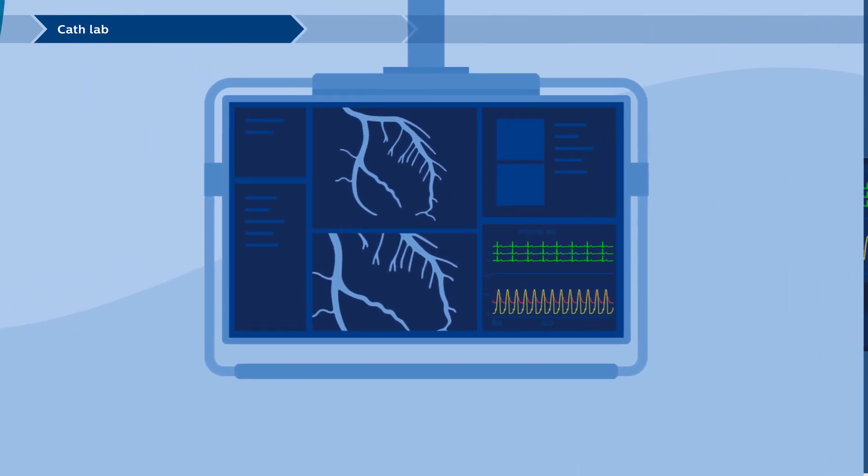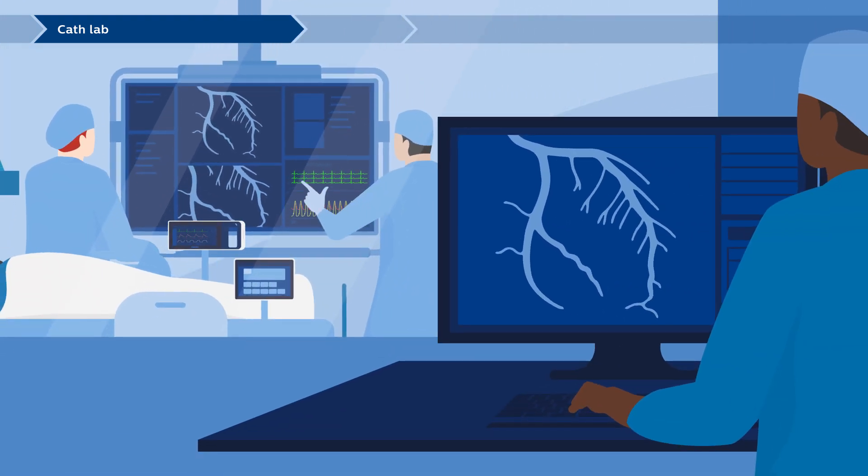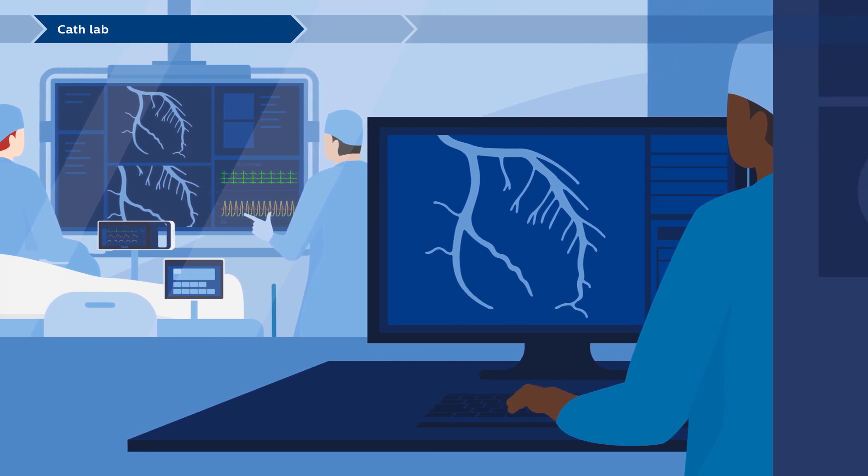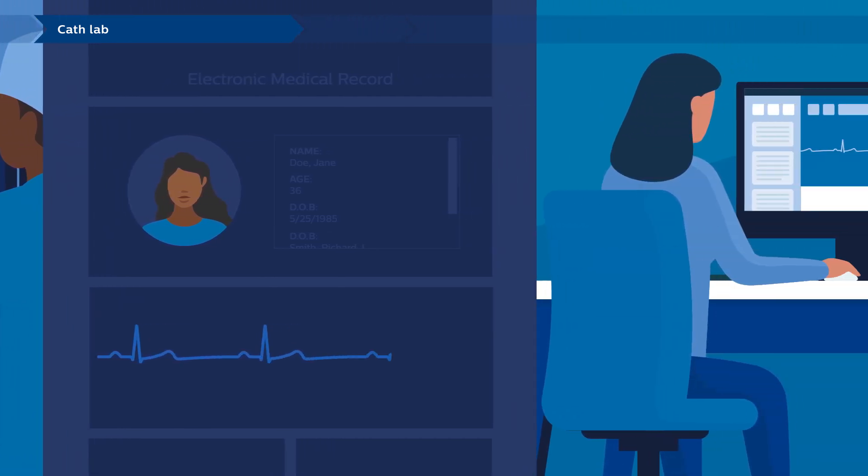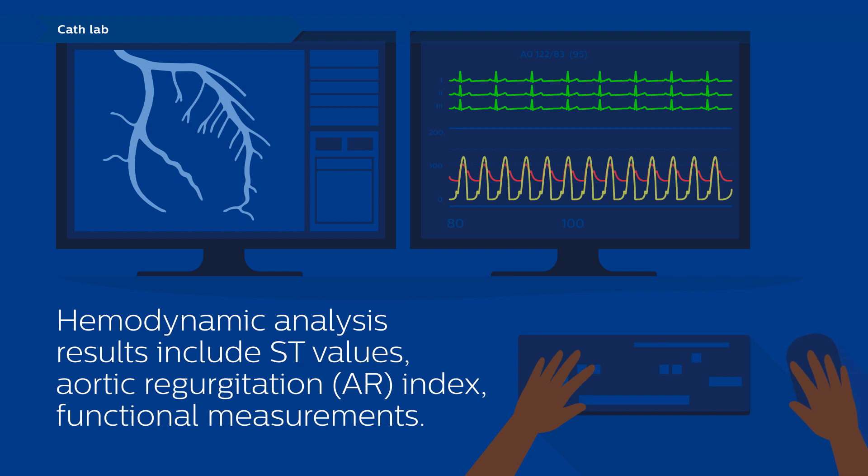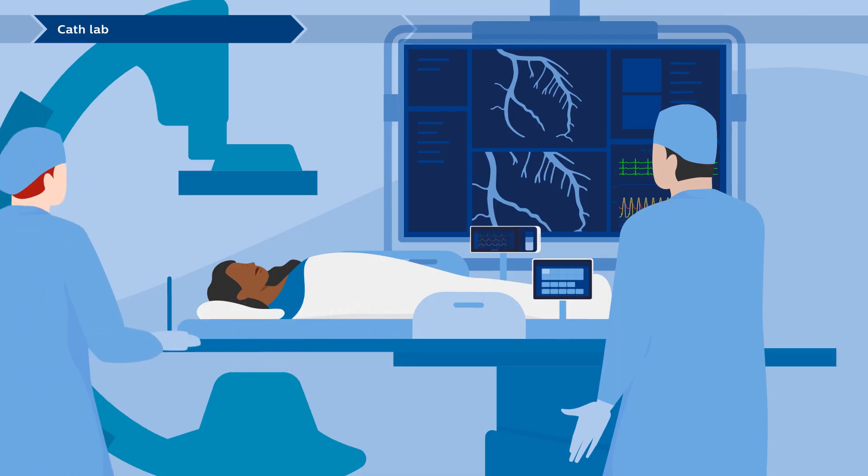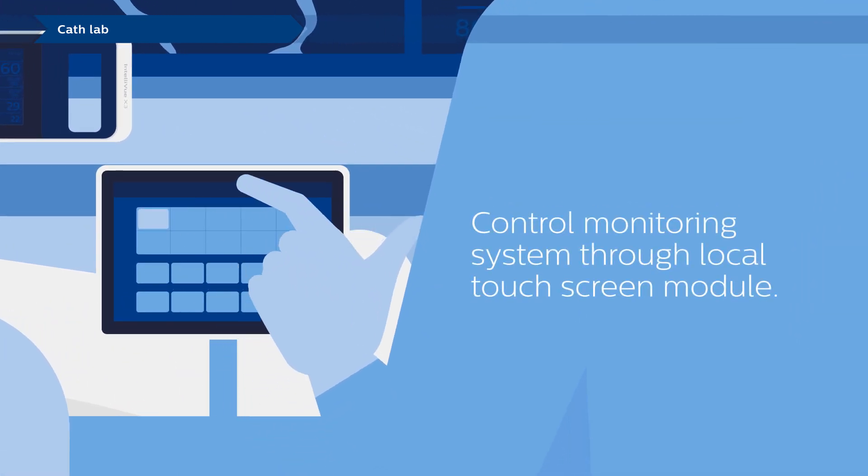Throughout the procedure, cath lab staff can monitor the patient's hemodynamic status. Data is displayed in the control room and on large displays in the exam room. Meanwhile, the hemo system sends high-integrity patient data to the cardiology information system and then to the EMR. Control room staff can perform hemodynamic analysis and display results in the exam room. In the exam room, the monitoring system can be controlled via a local touchscreen controller on the table.